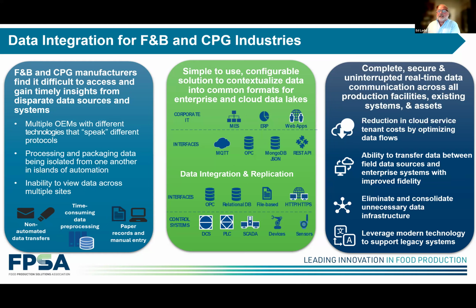But not everybody can speak that, so you fall back to Modbus TCP, probably one of the most prevalent protocols in the industry today. The problem with Modbus is everybody does it differently—it just defines registers, not how you use them, so everything has to be mapped. There are newer technologies like HART-IP, which deliver diagnostics and functionality from the device itself, all the way down to the plant floor, so you can understand performance and bring that data up to your management systems.